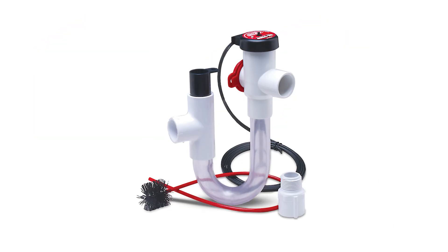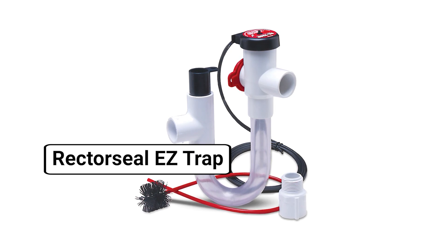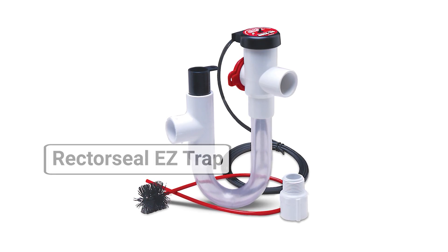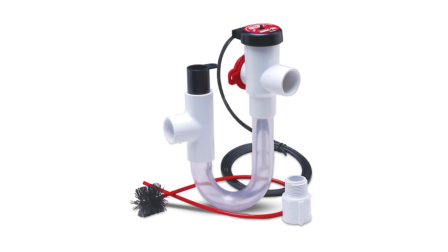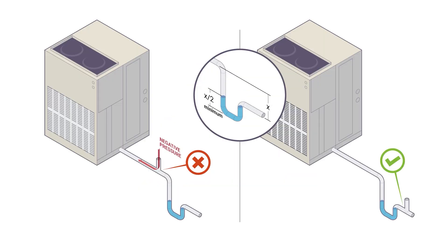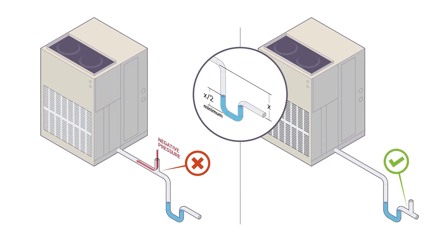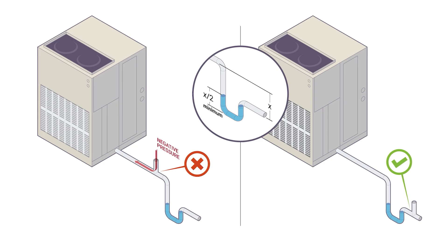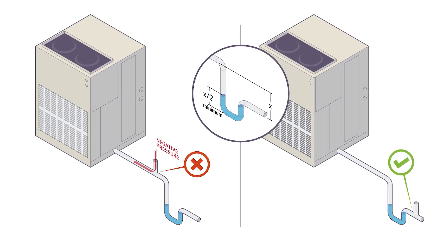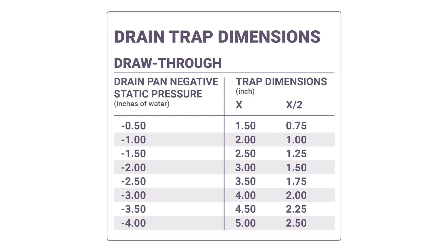They're currently using the RectorSeal EZ Traps, which are a one-inch trap depth, but the solution seems to be fabricating a deeper trap. There are formulas online but they're confusing, so a dive into the effect that negative pressure has on trap depth would be really helpful, especially this time of year.